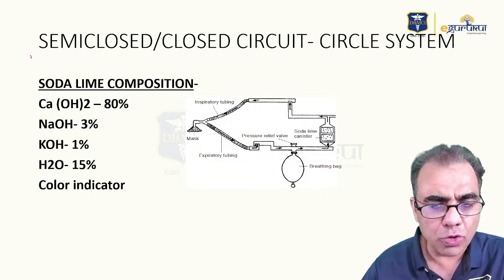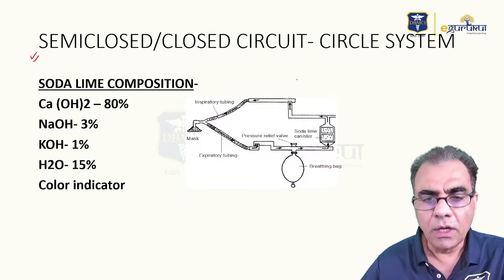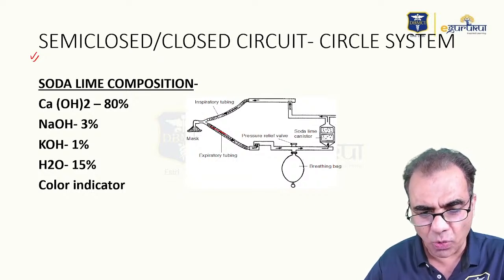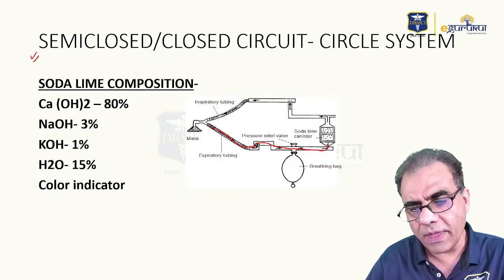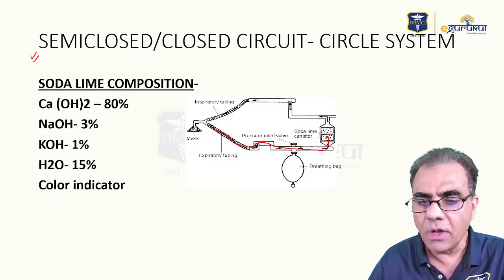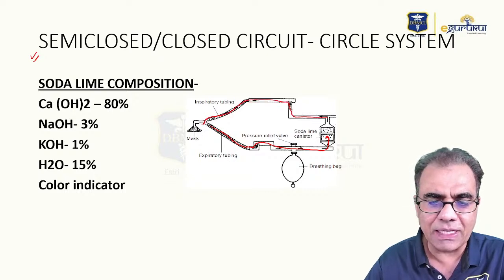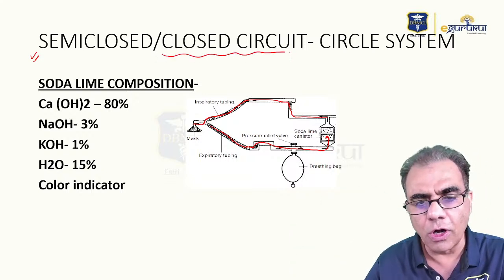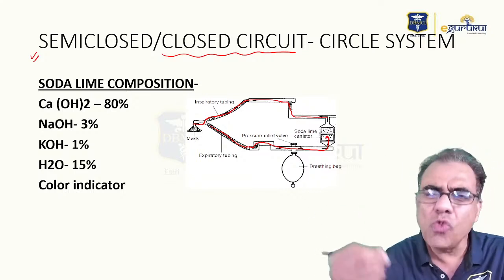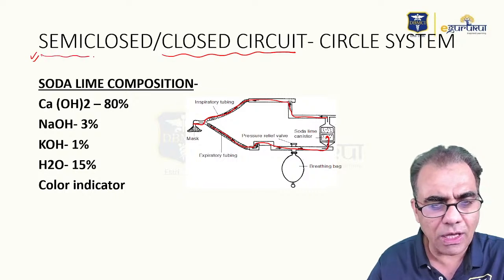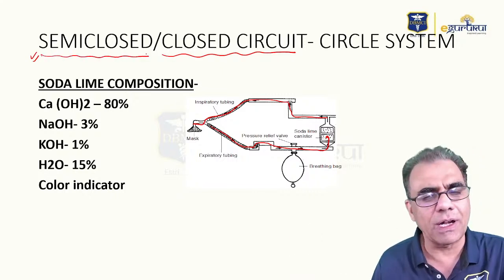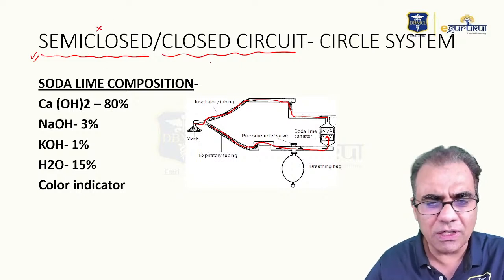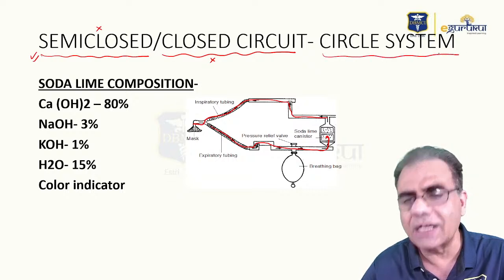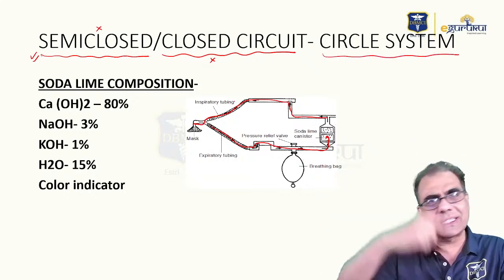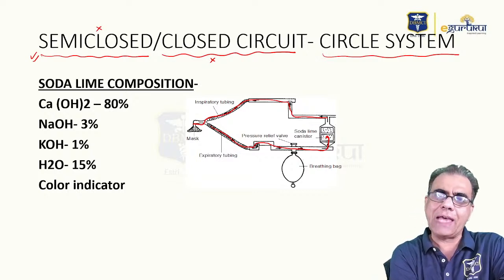Then semi-closed or closed. You can see in semi-closed and closed circuit, what will happen? Expiratory gases will pass through the expiratory limb, and from there they pass through this canister containing soda lime. Soda lime will absorb the carbon dioxide and the same gases can be reused. Now, since gases are not venting out into the atmosphere, it used to be called a closed circuit. However, some gases do vent out due to some leakage, so they are actually semi-closed circuits. But nowadays they say why have these confusing terms? The best term for these is circle system. Simply you can say the same gases are in circulation, so they are called circle system.